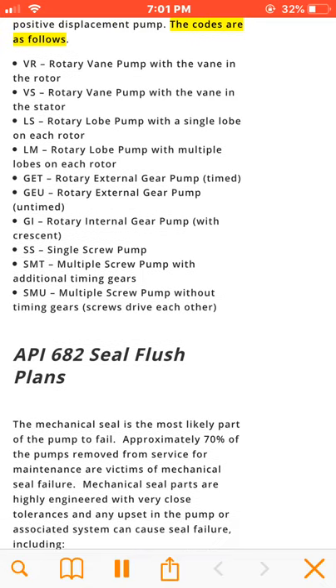The API 676 rotary pump codes are as follows: VR — rotary vane pump with the vane in the rotor; VS — rotary vane pump with the vane in the stator; LS — rotary lobe pump with a single lobe on each rotor; LM — rotary lobe pump with multiple lobes on each rotor; GET — rotary external gear pump, timed; GEU — rotary external gear pump, untimed; GI — rotary internal gear pump with crescent; SS — single screw pump; SMT — multiple screw pump with additional timing gears; SMU — multiple screw pump without timing gears, screws drive each other.